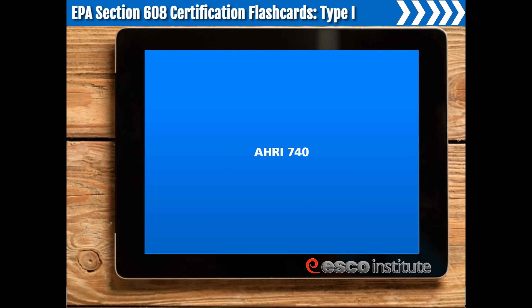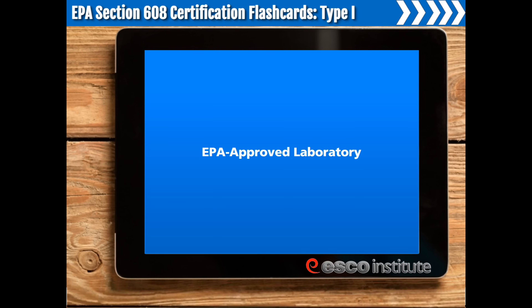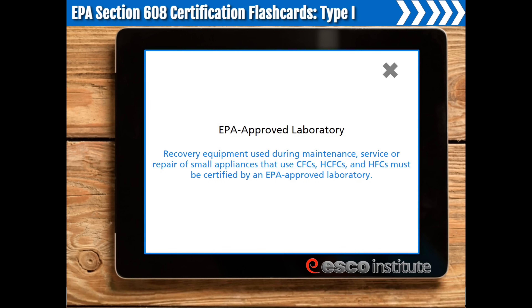AHRI 740. AHRI 740 is an industry standard that requires recovery devices used with small appliances to be able to recover 90% of the refrigerant when the compressor is operating, or achieve a 4-inch vacuum. When the compressor is not operating, the recovery device must be able to recover or capture 80% of the refrigerant using either a passive or active recovery process, or achieve a 4-inch vacuum. EPA-approved laboratory. Recovery equipment used during maintenance, service, or repair of small appliances that use CFCs, HCFCs, and HFCs must be certified by an EPA-approved laboratory.